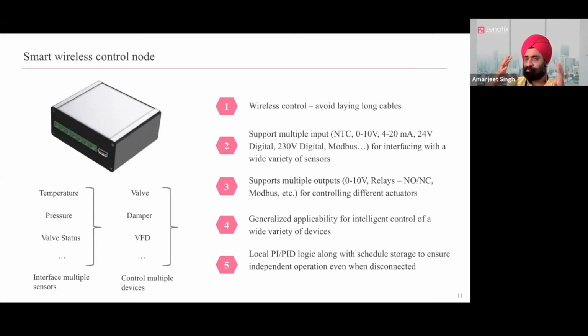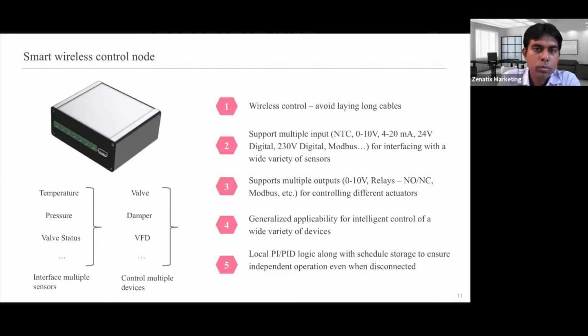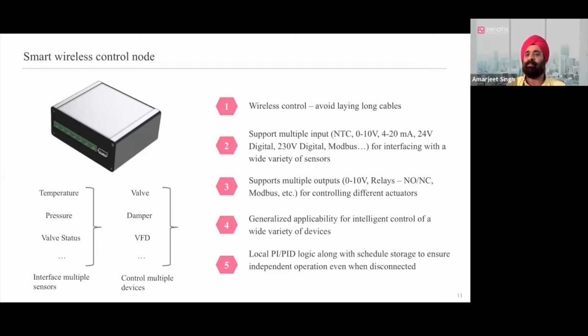Now, again, one of the concerns people have is, it's a wireless system. What if the wireless breaks down, right? The answer to that is, typically wires break down much more often than wireless. But even if there is a concern on that, the PID logic resides locally here, right? So even if this device completely gets disconnected from the gateway, this is the first level of redundancy that we have, that even if this device gets disconnected from the rest of the network, it will continue to function independently.